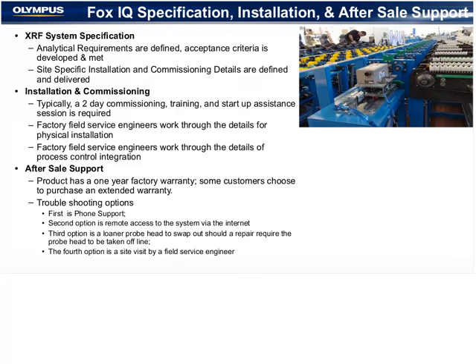The third option, say that your X-ray tube were to fail, is to have a loaner probe head sent to you to swap out while the repair is being made, the replacement X-ray tube. Some companies, particularly companies that have multiple systems, will actually buy a spare probe head and rotate it through like a spare tire so that they're always ready to just take 15 minutes to swap out if that were to happen and keep going. The fourth option is a site visit by one of our field service engineers.